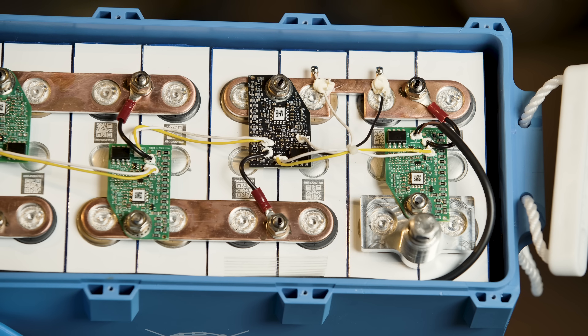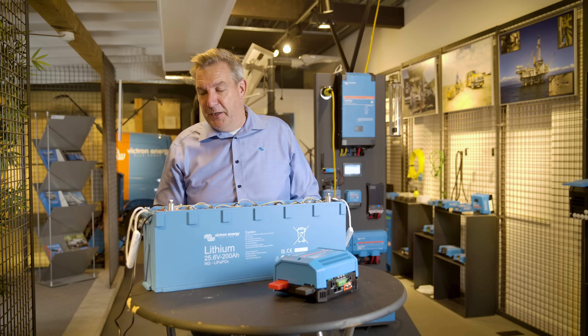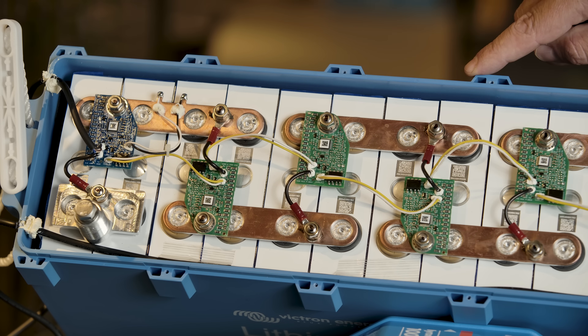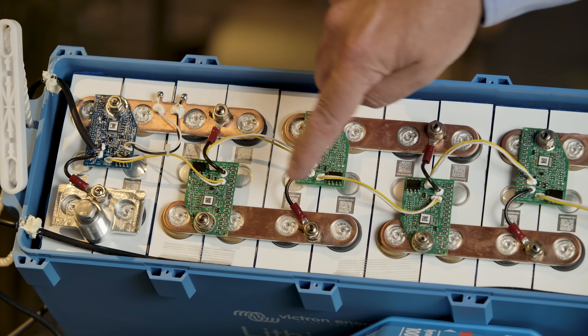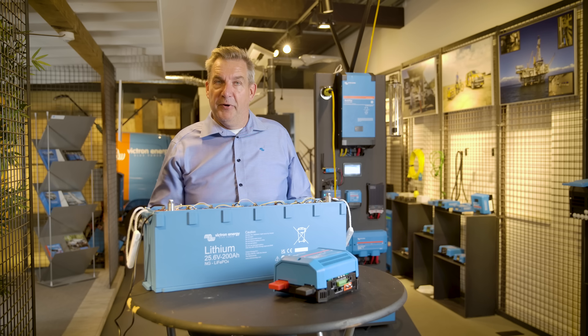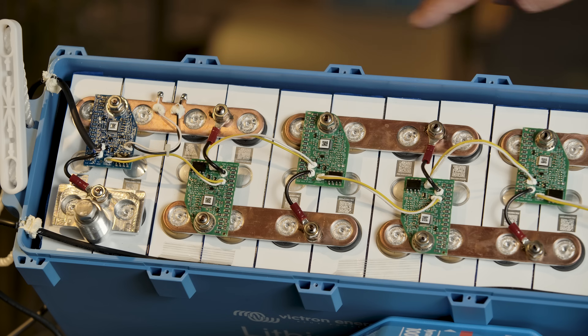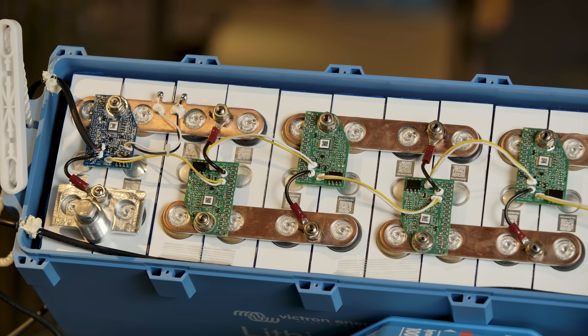In front of me I have one open battery, and I wanted to show you some extra things inside which are different from a Lynx battery. In this battery — a 24-200 — there are 16 cells, and each time two cells are paralleled. For the NG battery series, there will also be a 48 volt version, where the cells are all in series rather than two by two in parallel. The casing and closure are the same, the number of cells are the same, but the internal wiring is different. Inside the battery, on each parallel cell there is a circuit board capable of digitally communicating measurements to another circuit board.